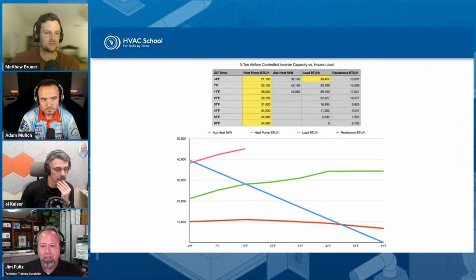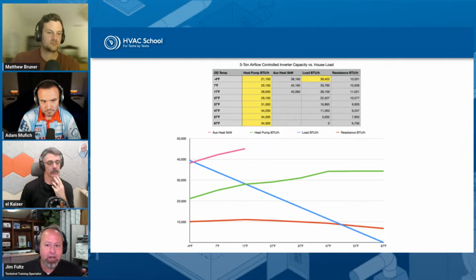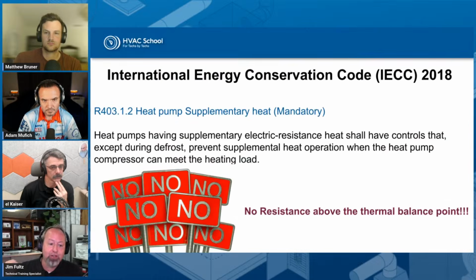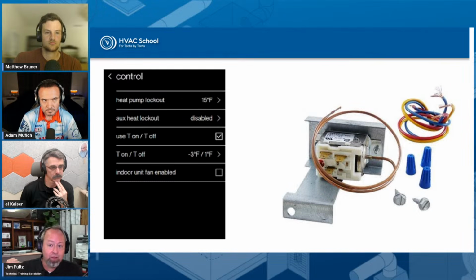Well, the question that I would get on that, and what I'm thinking about, is the technician saying, okay, how do we do that? How do we get that electric resistance heat to cycle? There's two ways to wire this. One, you have the call for the heat, the Y call, going to the heat pump. And if you take that power that's powering the heat pump, go to a thermostat that you put outside set at 17 degrees, when it gets to 17 degrees, it closes and it sends power back to the resistance heat. And at that point, the resistance heat's going to continue to be on constantly until the heat pump shuts off.